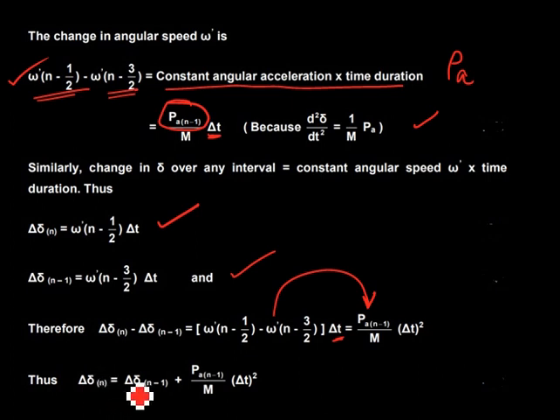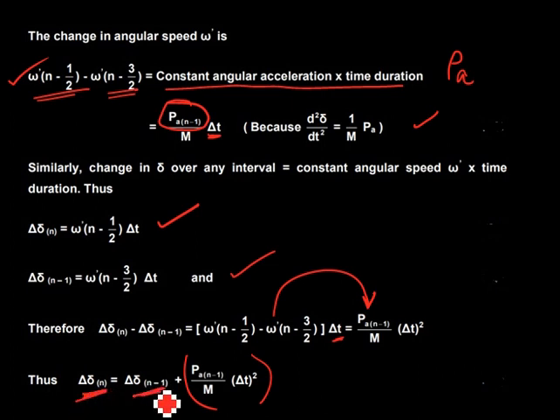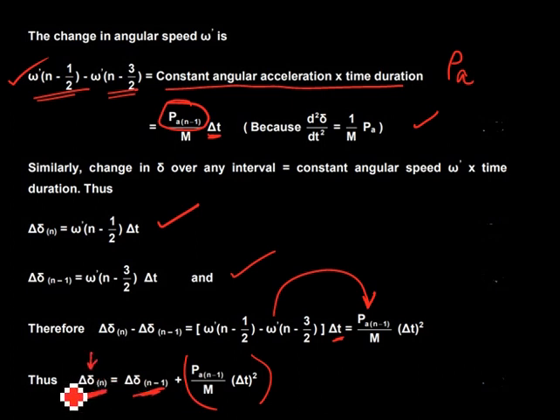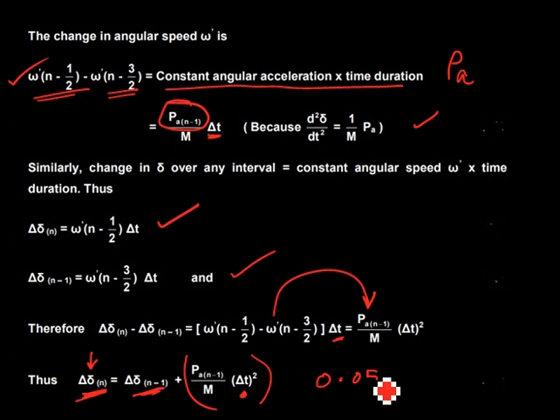This leads to the result: delta-delta(n) = delta-delta(n−1) plus Pa(n−1)·(delta-t²/M). The current change in delta equals the previous interval's change plus the accelerating power contribution. This is how the curve is built up. You can take delta-t as 0.05 seconds as the time step at the beginning of your calculation.